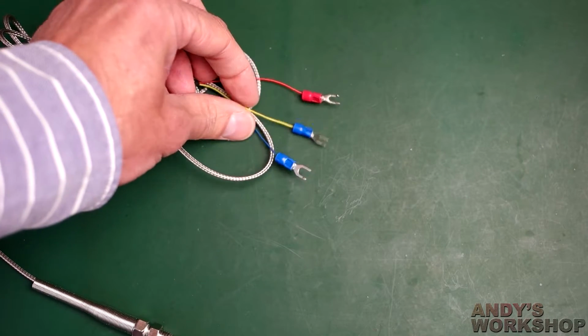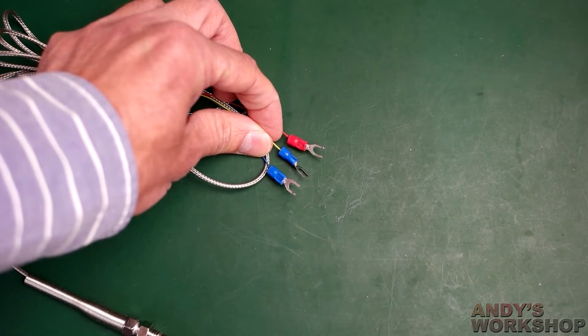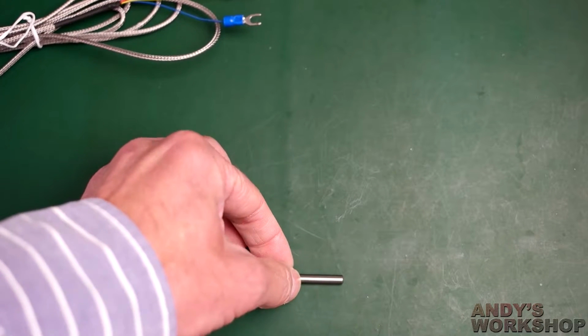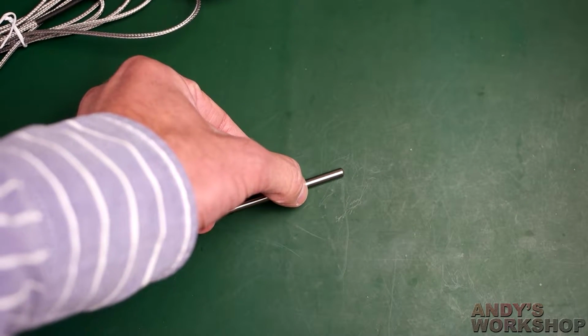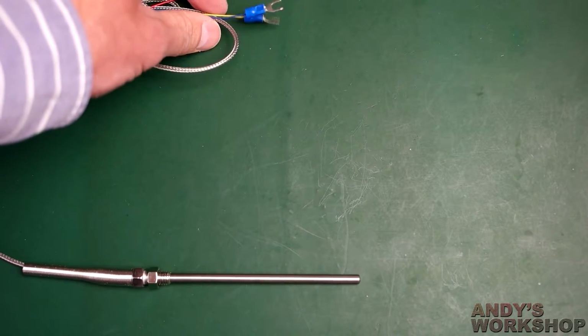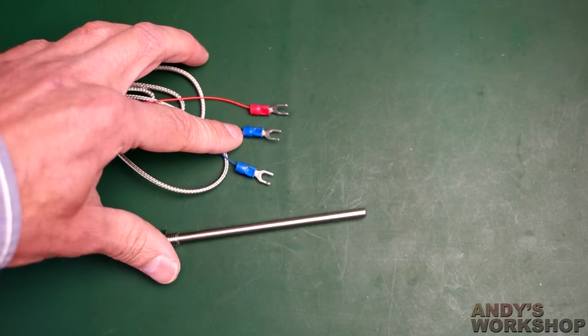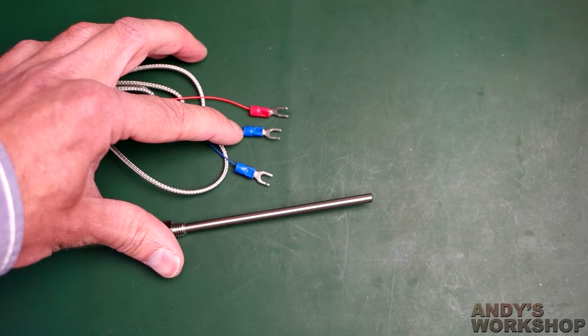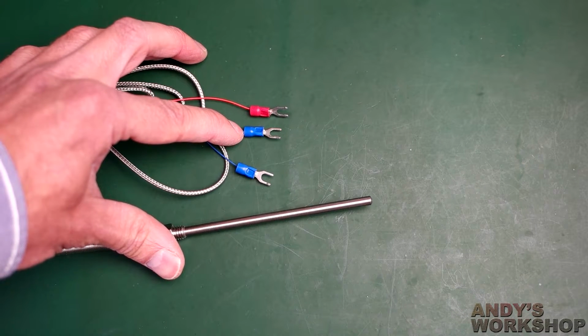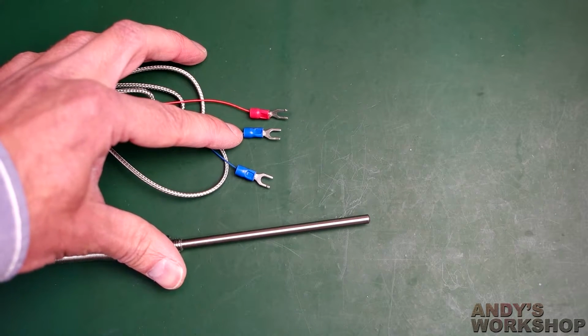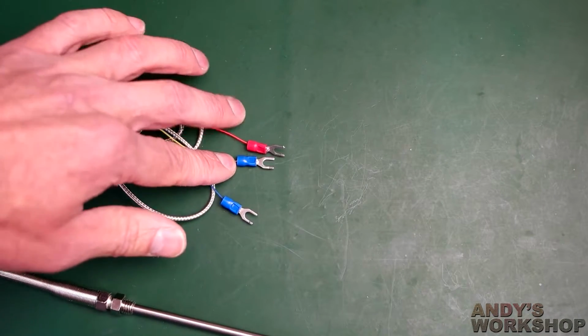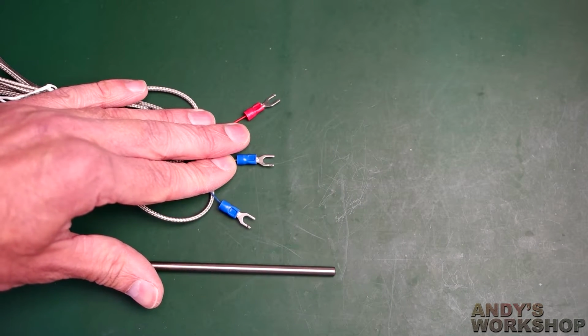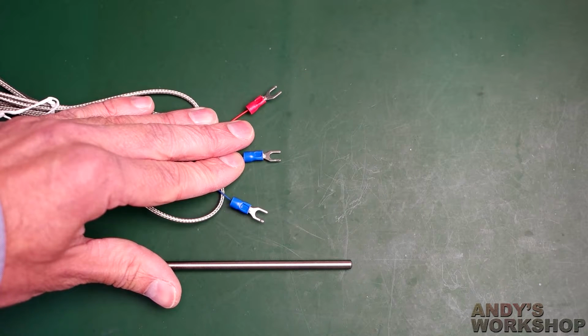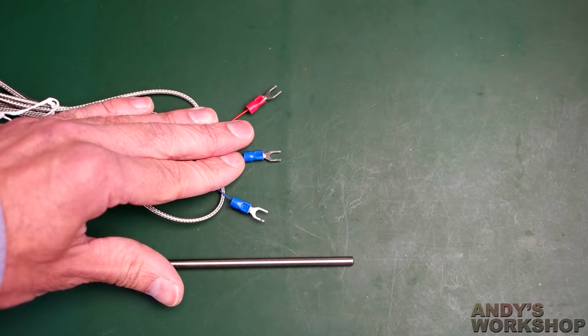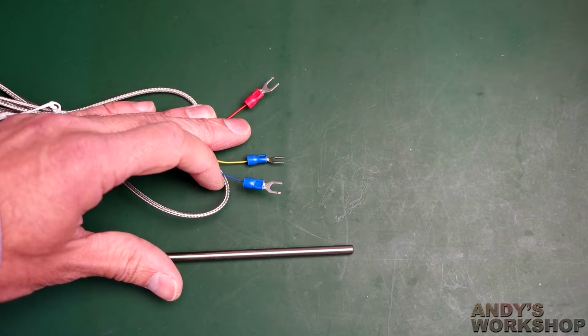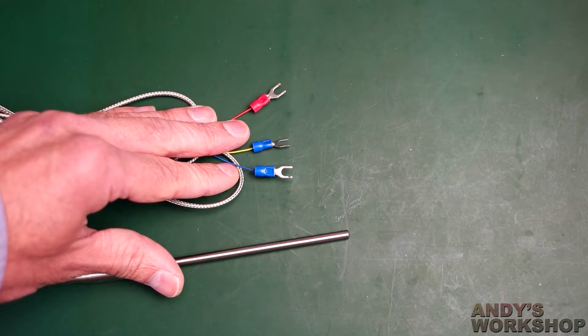This particular probe is a 3-wire type. What that means is that you can see by the colour coding there's 2 blue and 1 red. The 2 blue ones are connected to the same end of the resistance element down here at the tip of the probe. The idea is that you can cancel out the lead resistance by measuring the resistance across the 2 blues, because the range of resistance that a PT100 runs through is quite small, and just a small change in resistance can mean a big change in the actual temperature. And the red lead is connected to the other end of the probe. So basically, to take a measurement, you run an excitation current through the resistance element, and then you measure the resistance that comes back. Then you can convert it into a temperature.